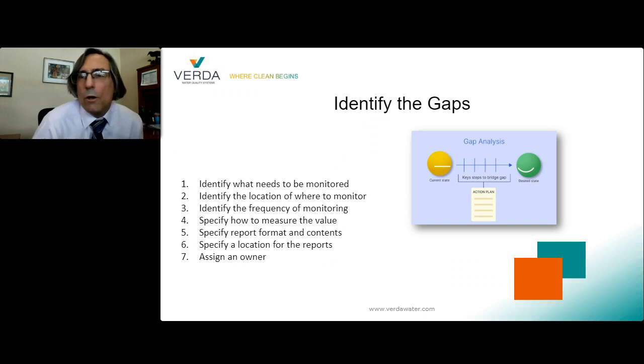To review what you need to know to have a successful water quality management plan in place, you must do these things. Identify all the things that need to be monitored, which will be water chemistry values and equipment health characteristics. Identify the physical locations of where you will be taking samples or where to read equipment-related values. Identify the frequency of monitoring for each. Specify the methods for how the value will be measured. This might be a water sample sent to a lab or reading pressure gauges and recording values.